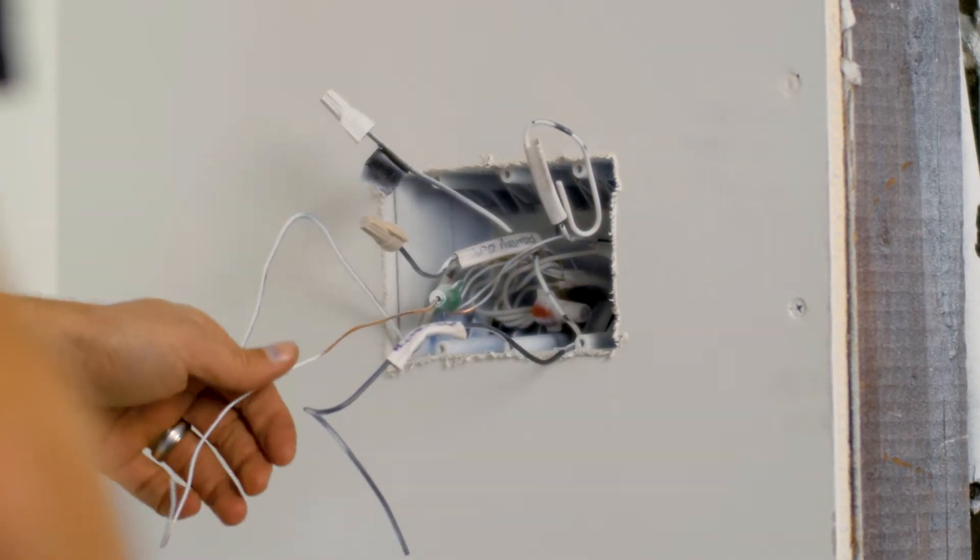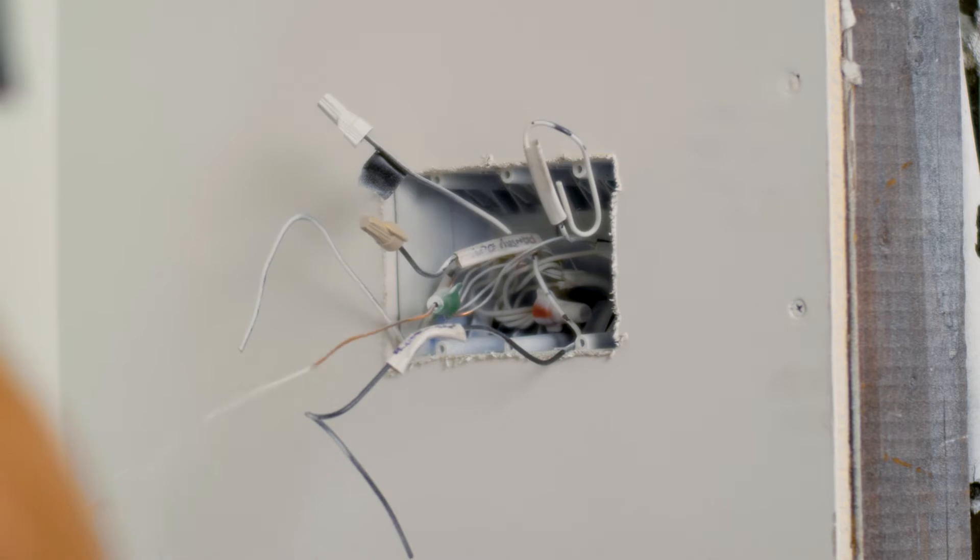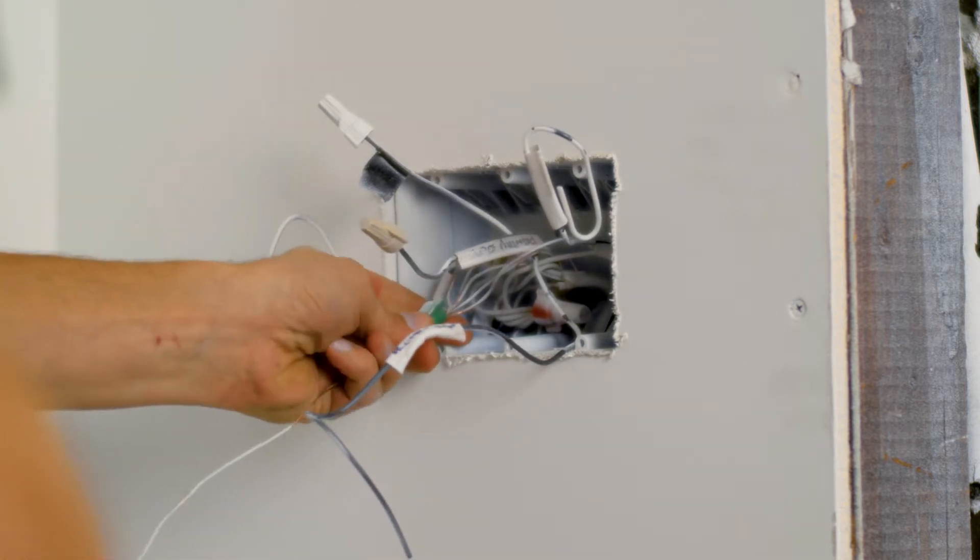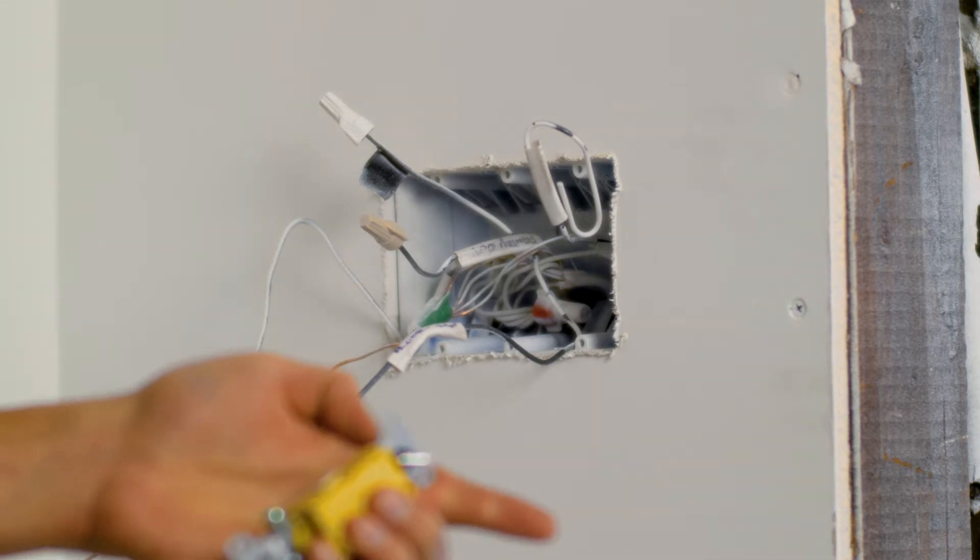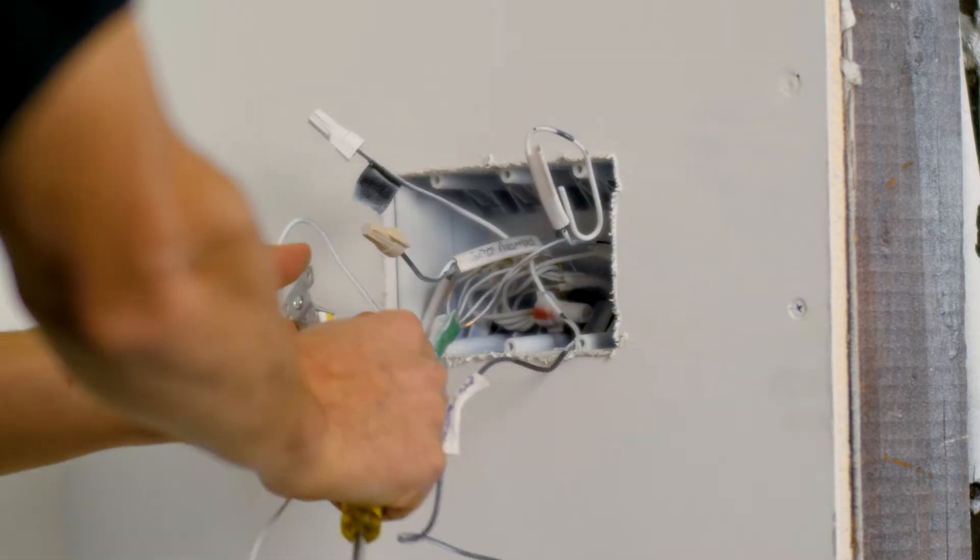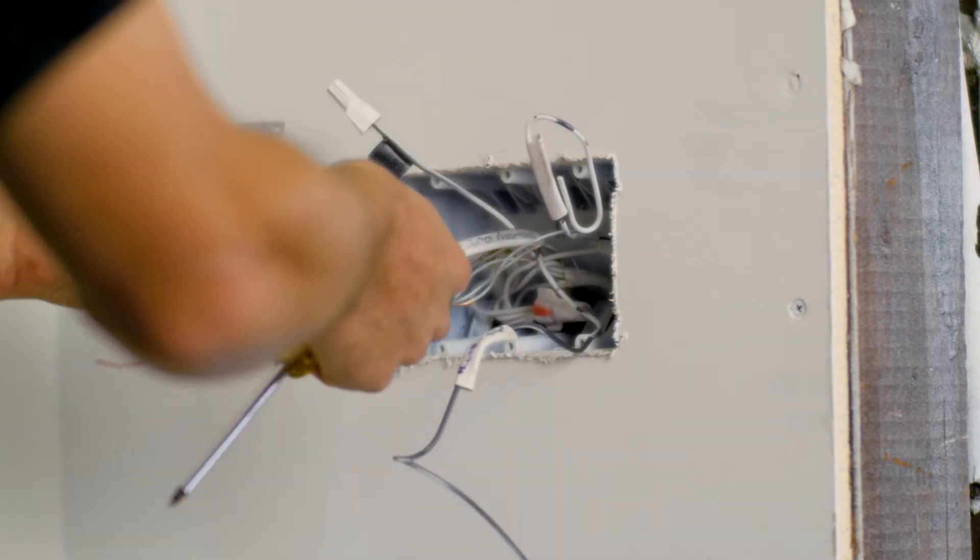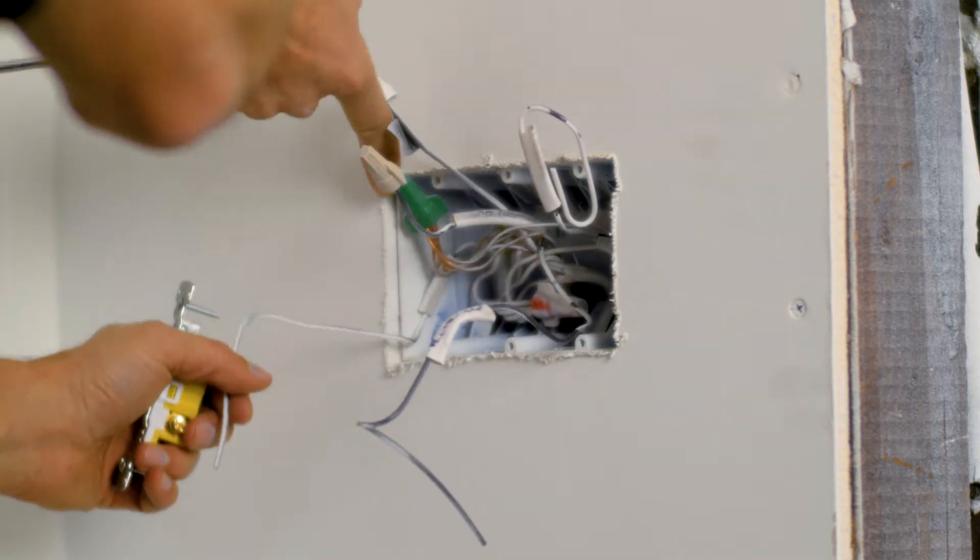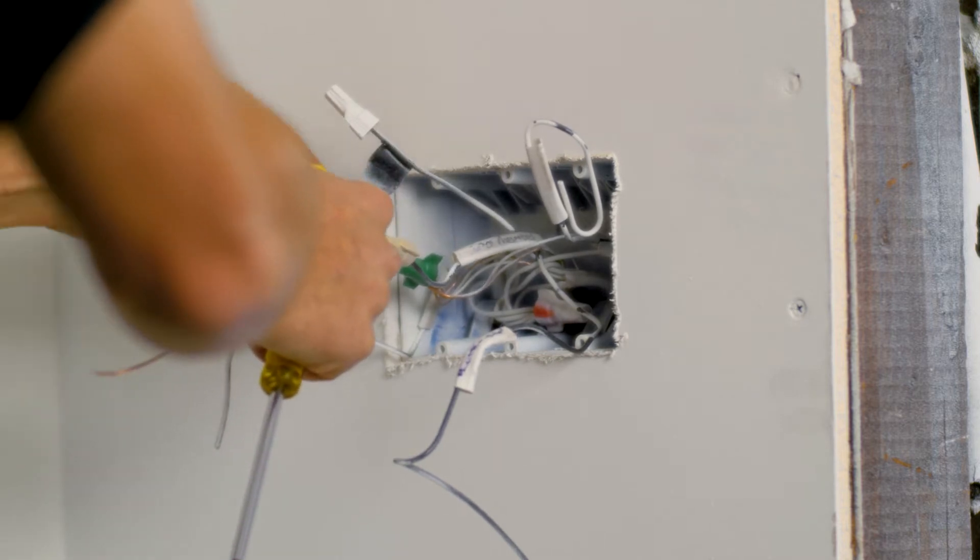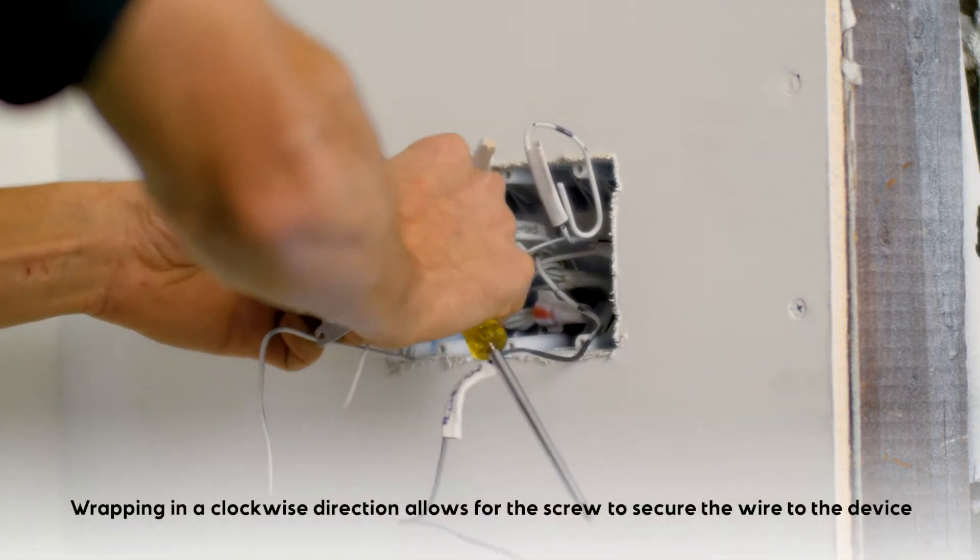Here I've got my ground which is long enough to wrap around all three because it's a three-gang box. I have three devices going in. All three ground screws on my devices, and I'm going to start with that. The orientation of my device ground is at the top, so I'm going to prepare for that. I'm going to wrap up in the clockwise direction.